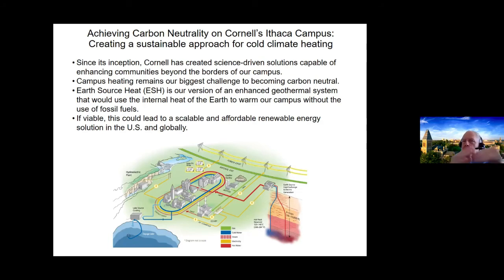Think about it simply: if I gave you 100 units of thermal energy taken out of the ground at, say, 80 degrees—just below the boiling point—and I tried to turn it into electric power, I'd get less than 5 units back as electricity because the efficiency is low. But if I use that same resource for providing heat, I'll get 90%-plus, maybe 95%. So the value of the heat delivered versus the lower amount of electricity delivered is significant.